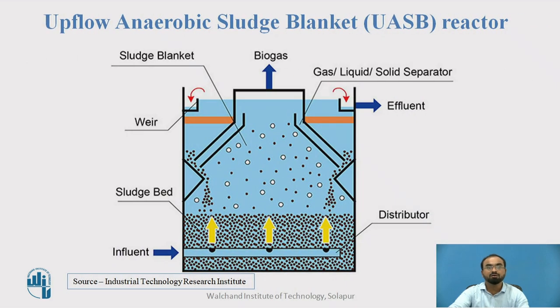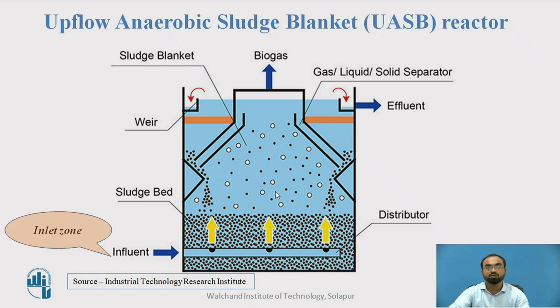Let us study how the UASB mechanism works. You can see the diagram where the influent enters through a lot of ports into this treatment facility. It is fully enclosed. As it is anaerobic in nature, no oxygen is allowed to pass inside the reactor. With the help of distributors, the wastewater coming inside the UASB reactor is spread out across the surface area. As the water passes inside, this area is known as the inlet zone — this is the first zone.